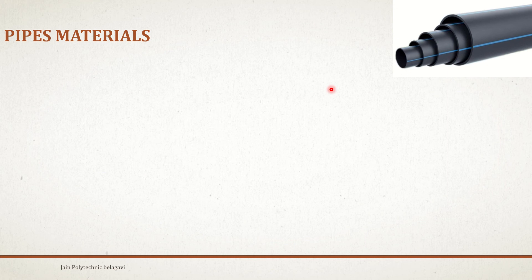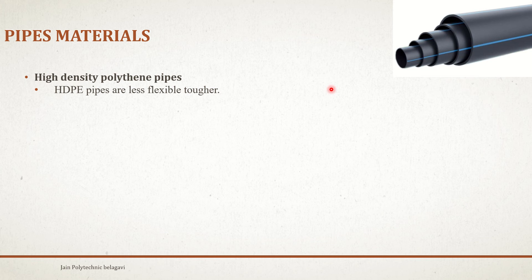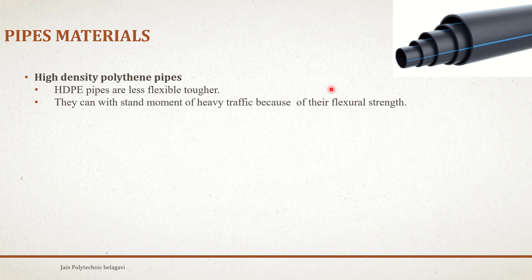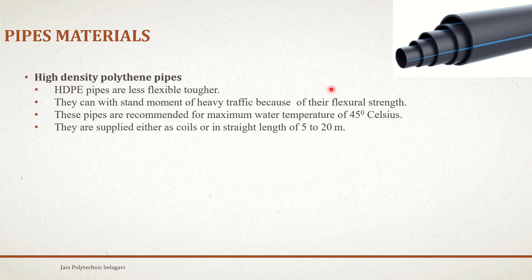Next we will go through high-density polyethylene (HDPE) pipes. These pipes are less flexible in nature and a little bit tougher. They can withstand movement of heavy traffic because of their flexural strength. They show slightly higher flexibility compared to regular plastic pipes. These pipes are recommended for a maximum water temperature of around 45 degrees Celsius and are supplied either as coils or in straight lengths of 5 to 20 meters.